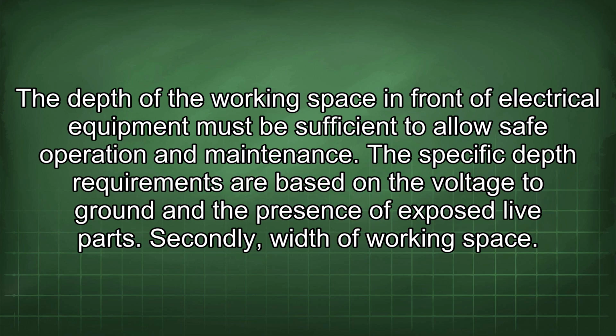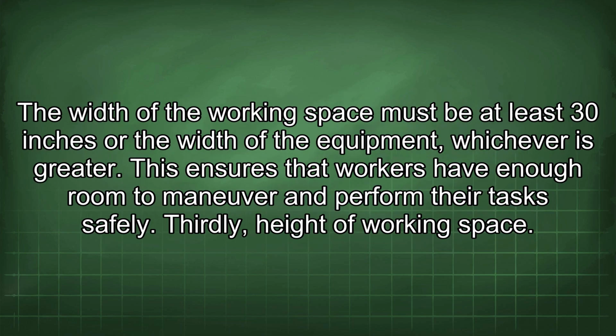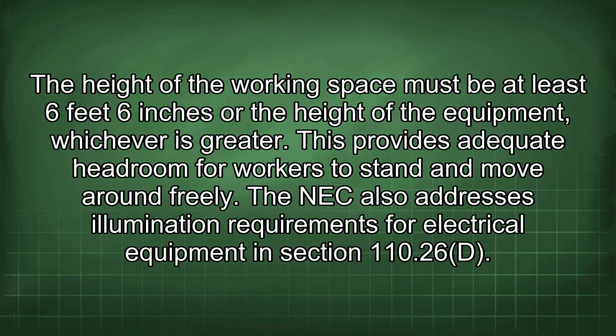Secondly, width of working space. The width of the working space must be at least 30 inches or the width of the equipment, whichever is greater. This ensures that workers have enough room to maneuver and perform their tasks safely. Thirdly, height of working space. The height of the working space must be at least 6 feet 6 inches or the height of the equipment, whichever is greater. This provides adequate headroom for workers to stand and move around freely.